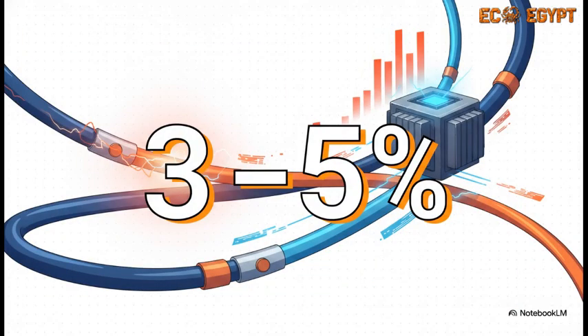And here is the absolutely critical engineering threshold for those LV cables, 3 to 5%. The voltage drop across these thick LV arteries has to be kept strictly under this limit. If you try to use a cable that's even a little too thin, the resistance causes the voltage to drop, which generates excess heat, and that will severely restrict the amount of power you can actually push into the transformer. It's a make or break metric.